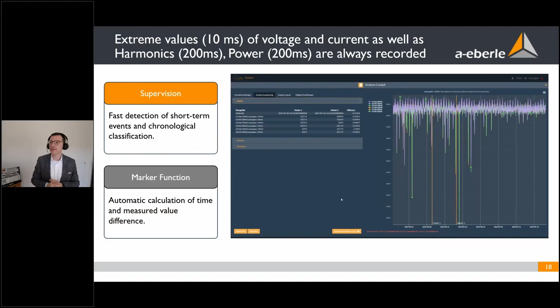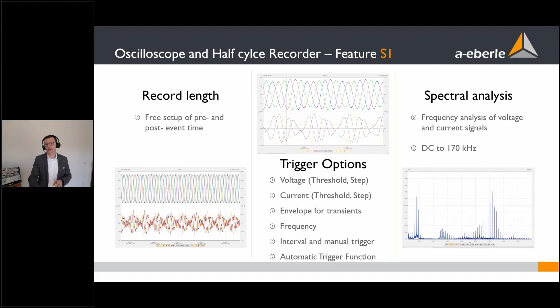With the opportunity of the feature S1, the disturbance fault recorder, you can get oscilloscope and half cycle recorders at the device. There is an opportunity to freely set up pre and post event trigger time. You have many trigger options. In case of voltage, you can set up 2 thresholds: line to line, line to earth, step, current, envelope for transient triggering, frequency, interval, and manual trigger, as well as other automatic trigger functions which can be used.